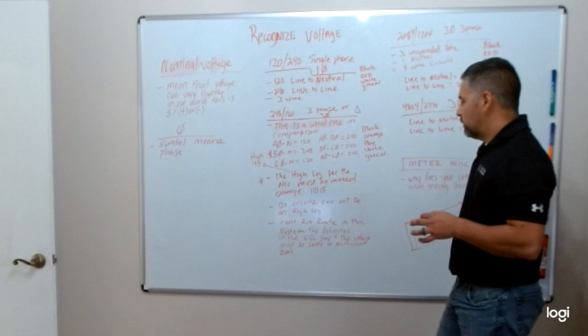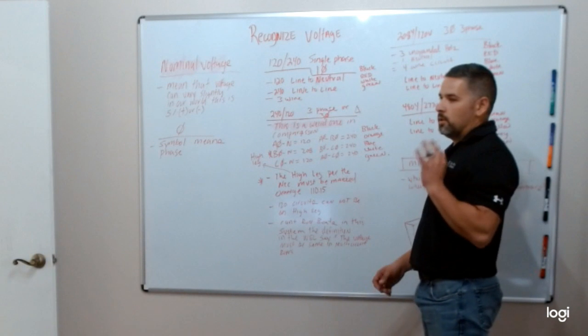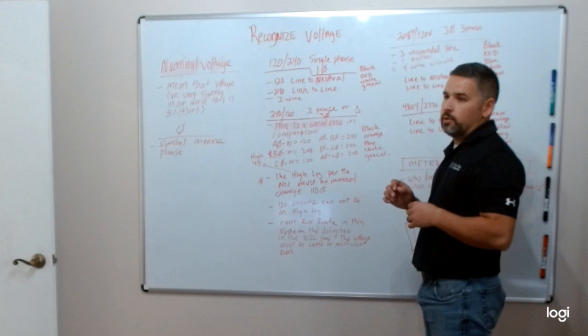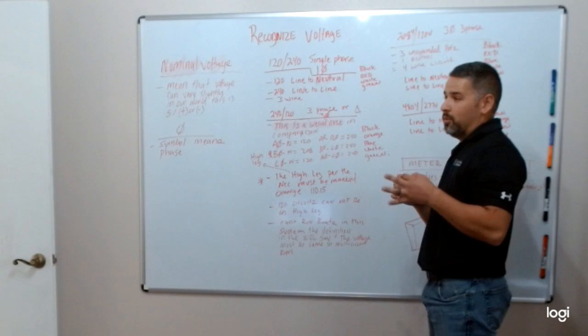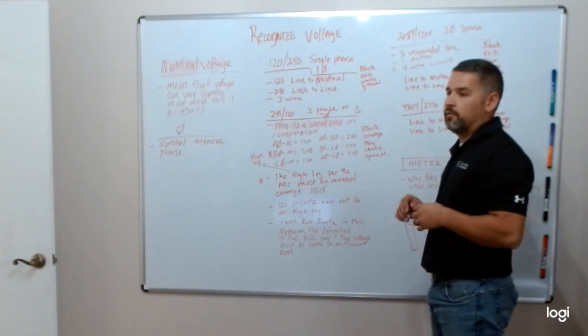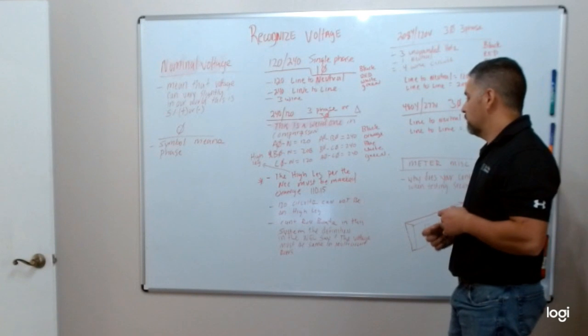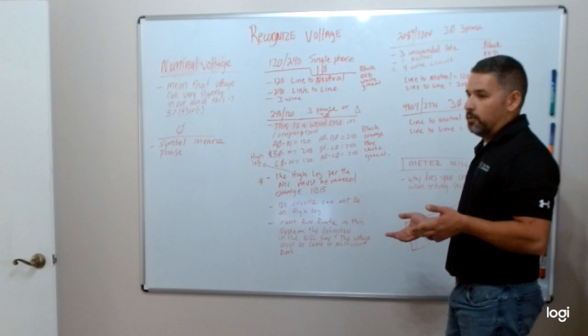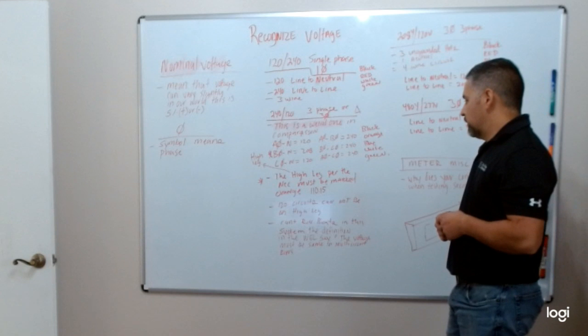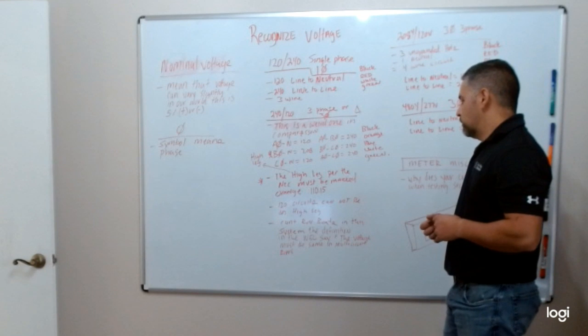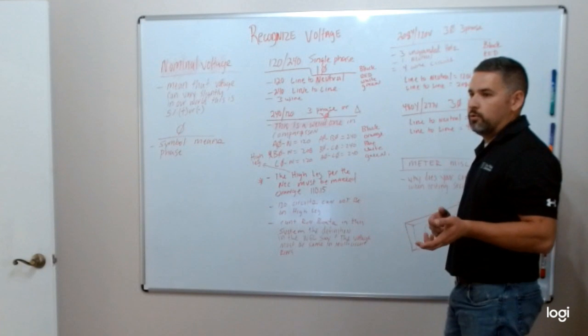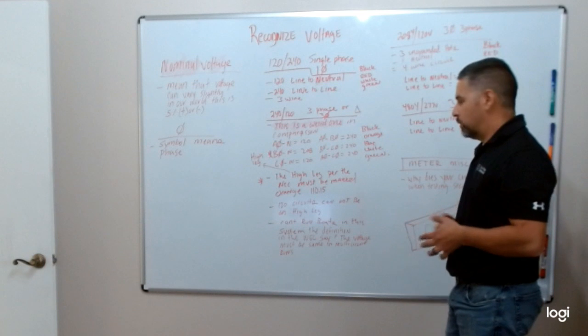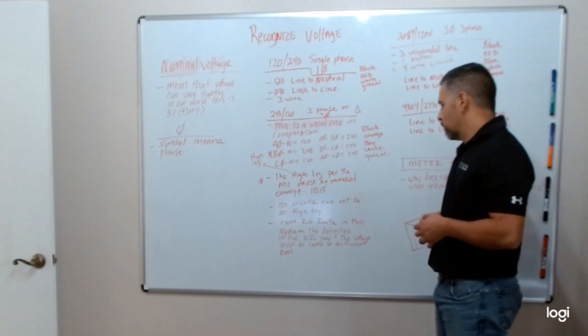So this has to be identified so that you do not put a 120 circuit on the B phase, because then you have the potential of messing up a receptacle, anything like that. Or just like putting a computer on a 208 system would definitely screw that up.